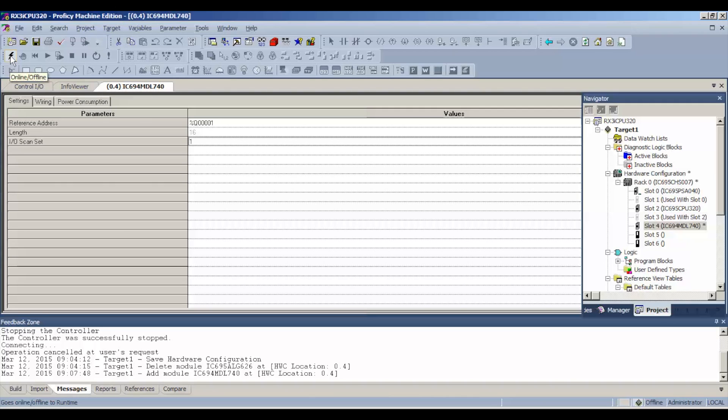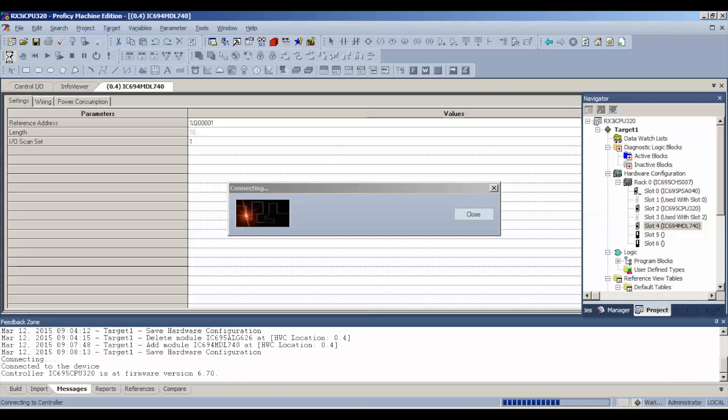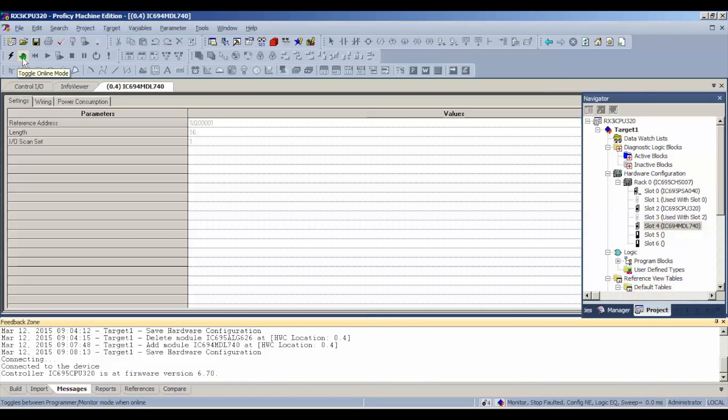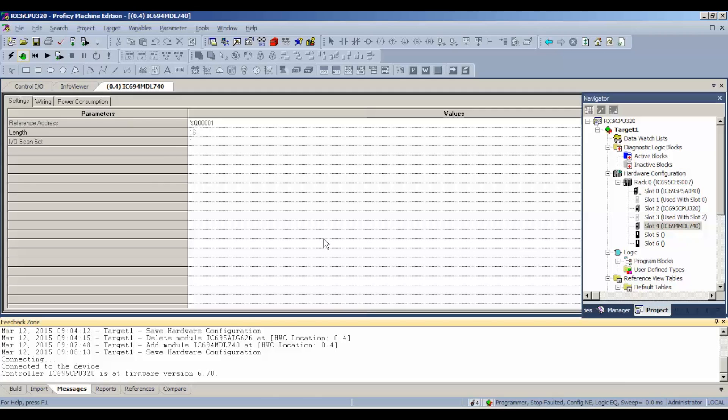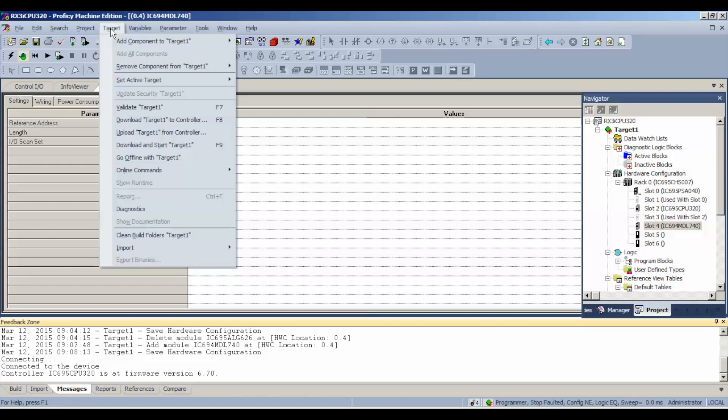So we want to connect up to the controller once that's all set. Once we've made connection, we're going to hit the green handprint to toggle us to online mode. Now what that means is we're in programmer mode. Our outputs are stopped and disabled or in this case faulted, which is fine. Configuration is not equal. That's because the processor was handling a different task before we've asked it to test the MDL740.